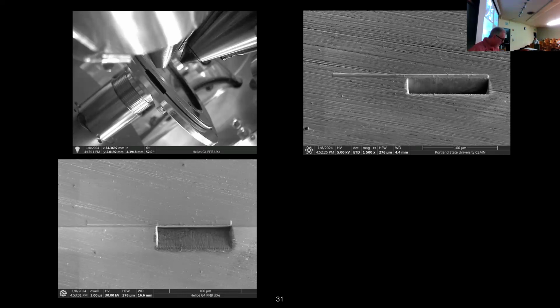And we can do imaging with the ion beam. It is destructive. You can get almost all of the same signals out of an ion beam as you can from an electron beam, but you cannot get backscattered electrons, because backscattered electrons are primary electrons from your electron column that have interacted inelastically with an atom. So this would be a secondary. This is actually the way this detector is configured. Instead of being an ion image, it's a secondary electron image using the ion beam as the generation source. So our sputtering is taking, as we're taking materials off, we're generating secondary electrons, which are defined in the physics world as having voltages of 50 electron volts and less.